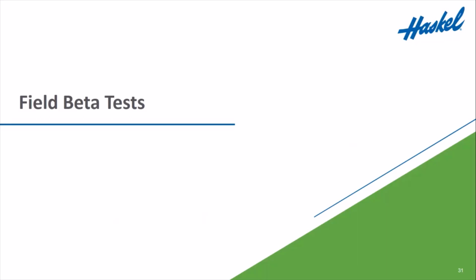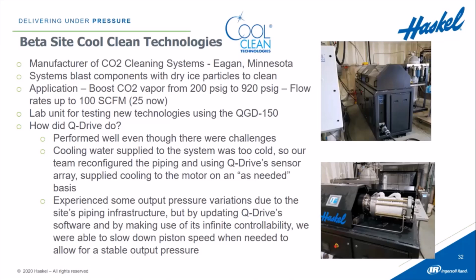Now, QDrive has been proven because we've had a couple of field beta tests done out there, and I'd like to talk to you about a couple of them. The first one is Cool Clean Technologies out of Eagan, Minnesota. They produce systems that blast components with dry ice particles for cleaning. Now, their application, they needed to boost CO2 vapor from 200 to 920 psi with flow rates up to about 100 standard cubic feet a minute. And what we did was we installed a QGD 150 in there last summer.